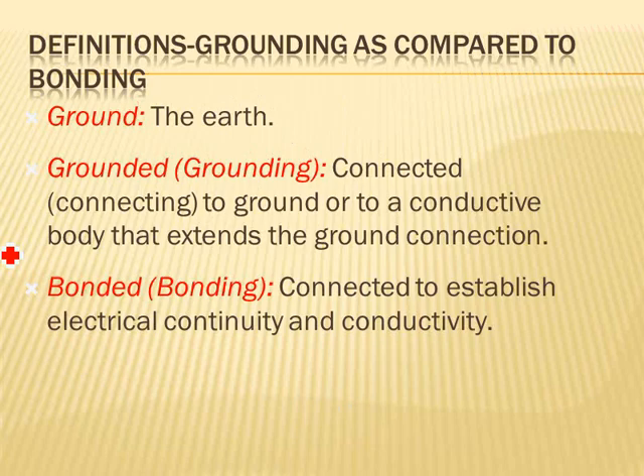So, straightforward, a couple of definitions. Ground is Earth. So when we invade the moon and inhabit it, we have to redefine what ground is, right? Grounded conductor: you're going to hear the word grounded conductor, intentionally tied to the ground. Or grounding, connected: the word that we use, connected or connecting to ground or any metallic object to extend the existence of the ground, like that ground bar that we put at the bottom of the electrical room to tie to. Bonded or bonding: connected to establish electrical continuity and conductivity. It used to confuse me all the time, guys.